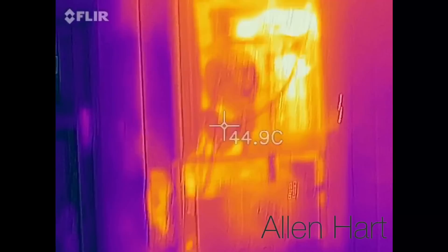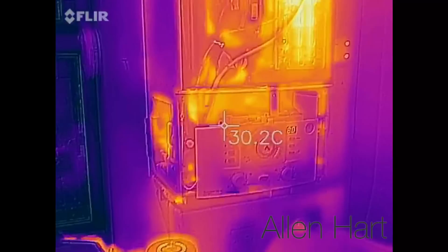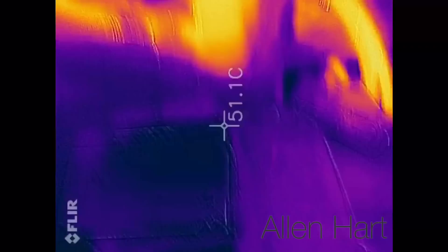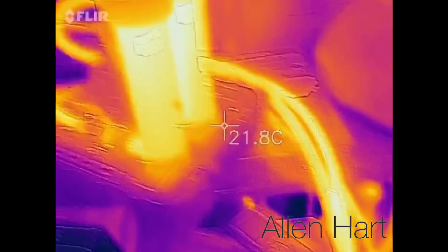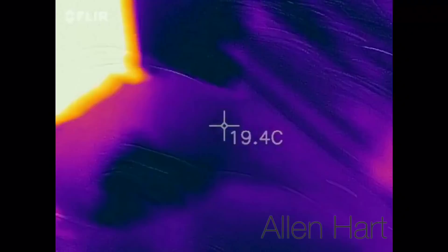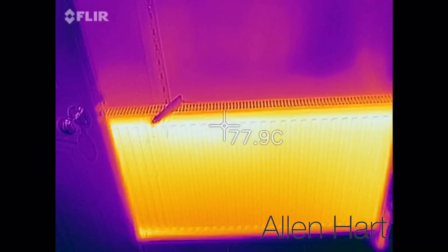Today we've been power flushing the boiler in Leeds — the system wasn't getting to temperature. We fitted a Fernox TF1 Omega filter. It's going through a MagnaCleanse at the moment and we've got the dirt and debris out of the system. As you can see there, the radiators are lovely and warm.